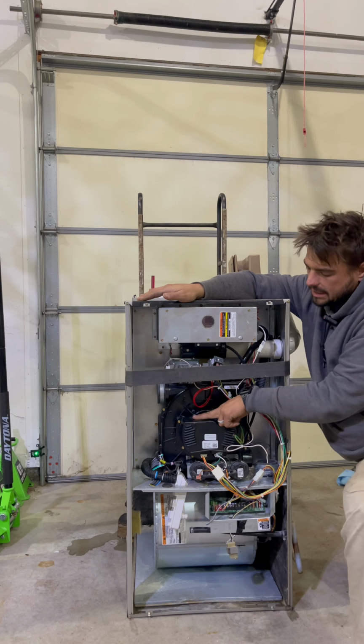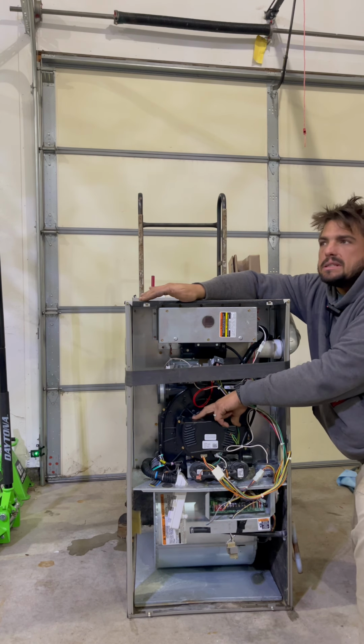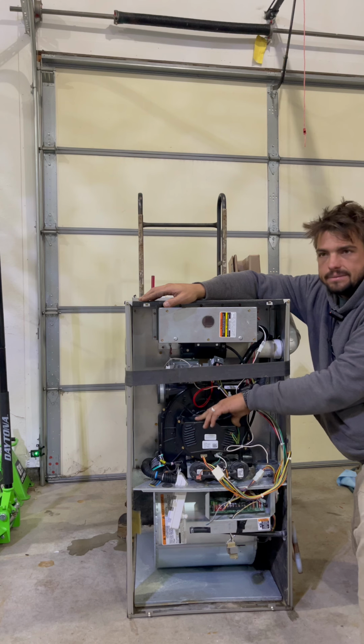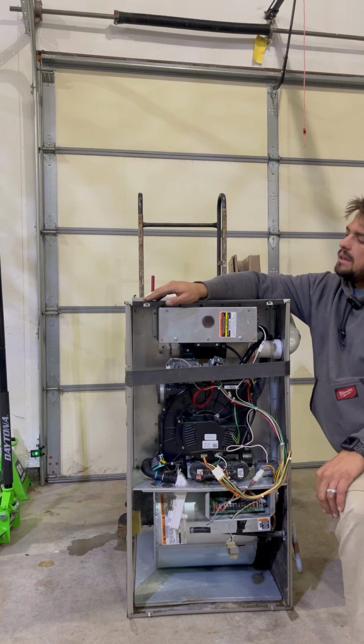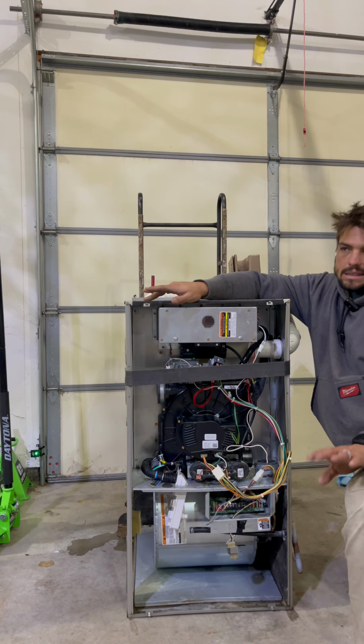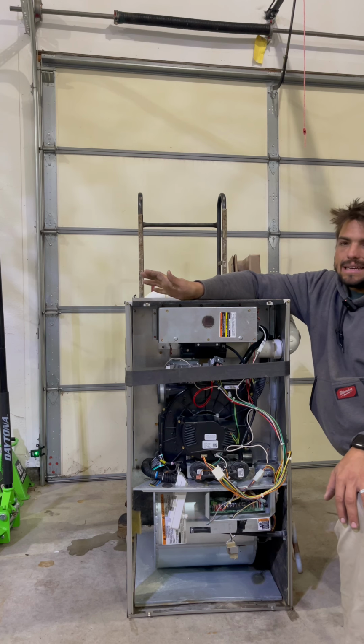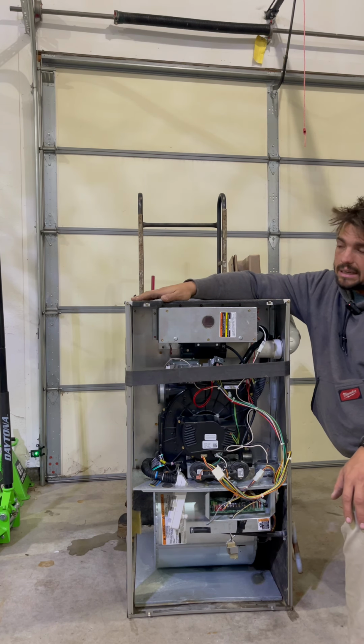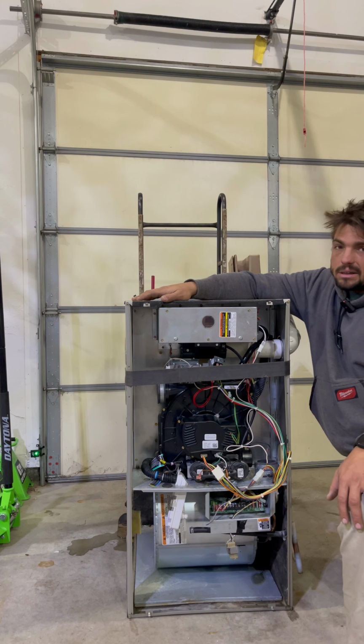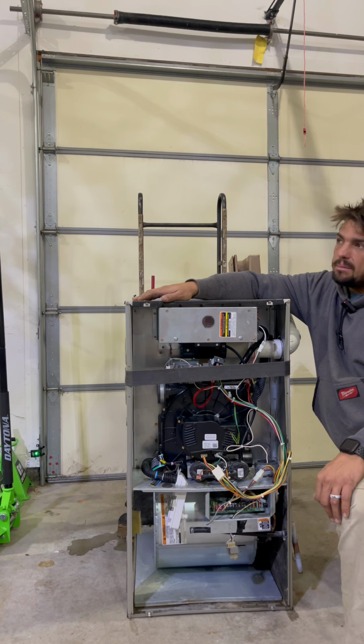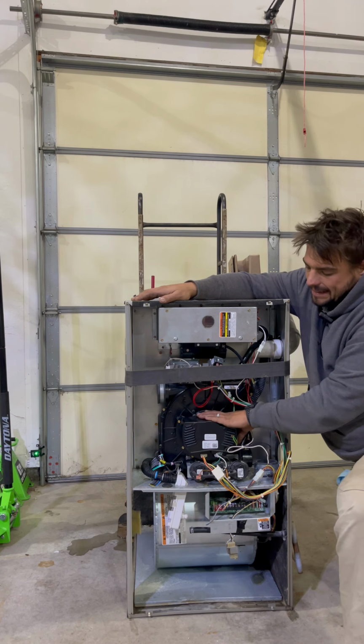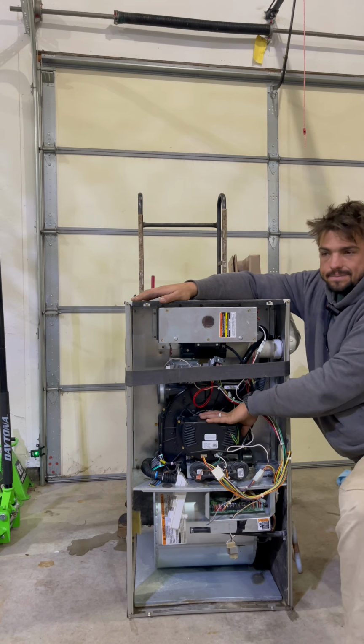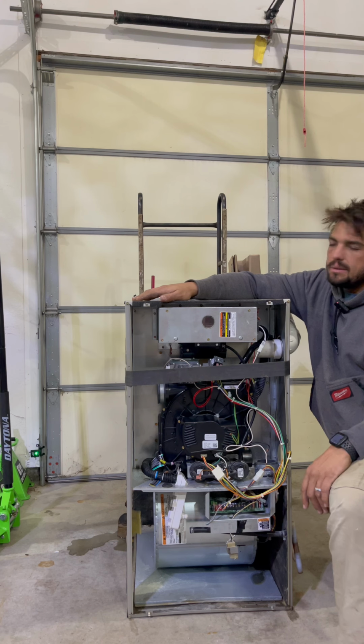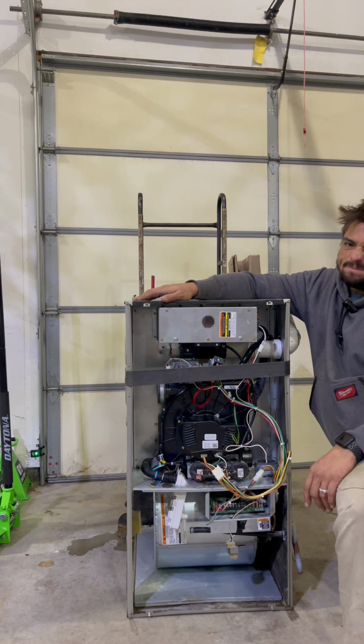For a modulating unit, kind of like this one, you'd be somewhere in the $5,500, maybe $6,000 range. You get a couple percent more efficiency. That single stage unit I was talking about is like 96% efficient, which is pretty good. You're only losing 4% of your potential heat there, and that's pretty darn good. Whereas a modulating unit is maybe 97.5%. So you're adding an additional $1,000 risk to a future repair for maybe 1 to 1.5% more efficiency.